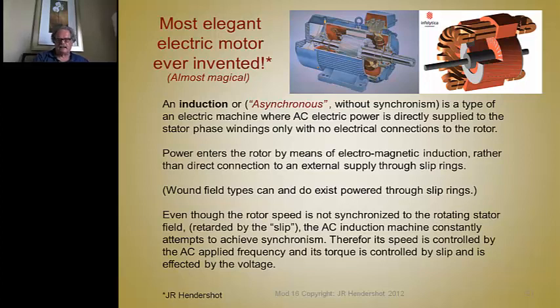Although, having said that, it is possible to take the rotor in the machine that you see up there in either one of those pictures, and instead of die casting aluminum conductors or copper conductors down the slots, you can wind a three-phase winding there, put slip rings on it, and control it with an external inverter.